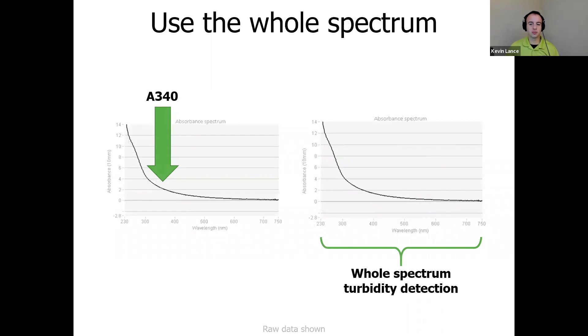So Stunner's RNA LNP turbidity correction is a dramatic improvement on classic methods. Old school turbidity correction takes just the absorbance signal found at 340 nanometers, called the A340, and subtracts it from the RNA signal that you have to care about. Typically for DNA, that'll be at 260 nanometers. By comparison, Stunner's RNA LNP turbidity correction matches the library of spectra across the full gathered spectrum to find the best fit. The end product is a picture of the turbidity over the complete 230 to 750 nanometers. Using the whole spectrum opens the door to a more comprehensive turbidity correction and allows you to begin to see details on the UV-Vis absorbing molecules present in your sample. So if you've got the whole RNA LNP spectrum, use it.